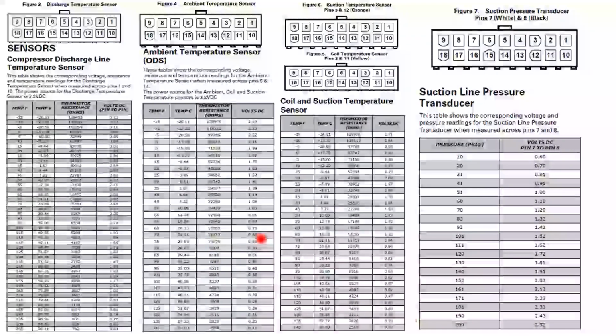I like taking volts DC because I can leave everything powered on. So I'm going to go across pins 5 and 14. Volts DC, if it's 70 degrees out, it should be at 0.68 volts DC. So all these charts are in the service facts. And again, the only one that has to be done by volts DC is the suction pressure line.